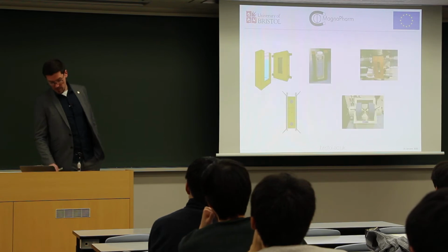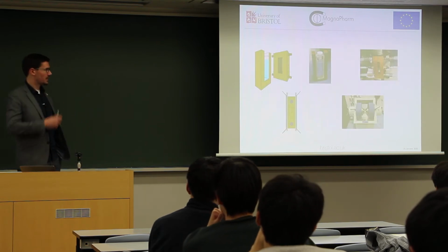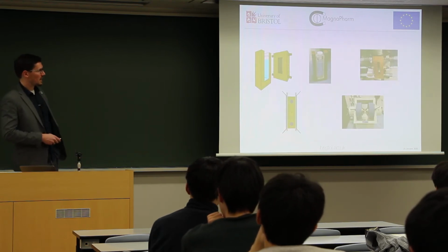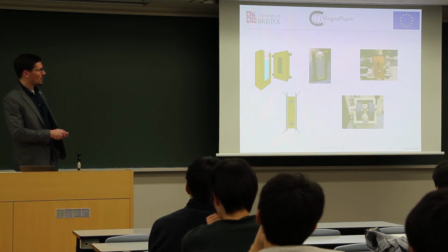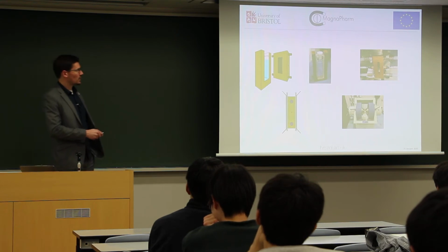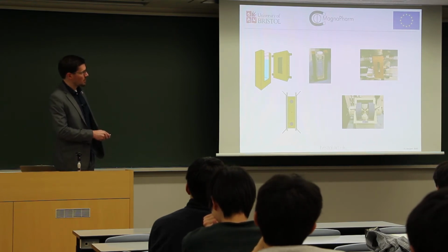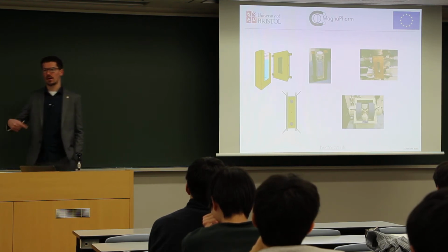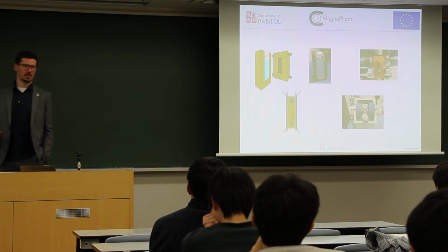So back in Bristol, this is where we designed this piece of kit. This is basically a copper block with a horseshoe-shaped holder. We slot the cuvette in like this. We push it into the copper block. This is a water pipe in. This is a water pipe out. So we flow water through the copper block nice and fast so we can keep the temperature nice and stable.